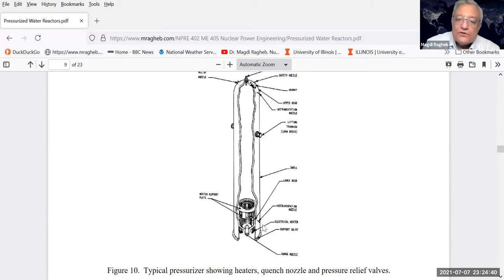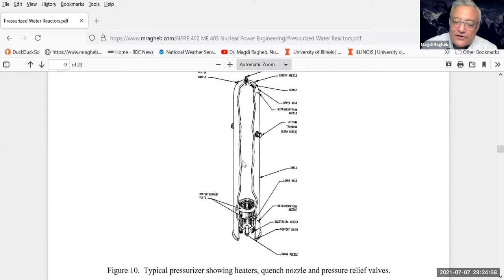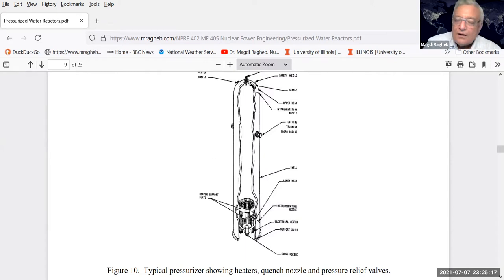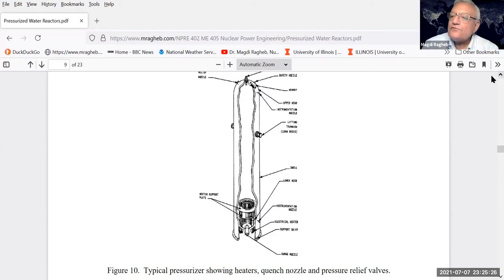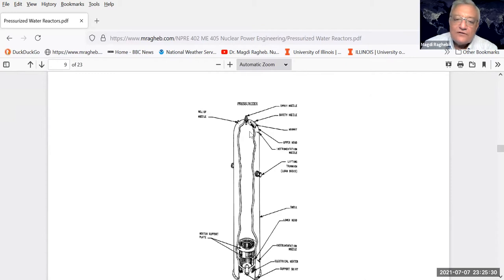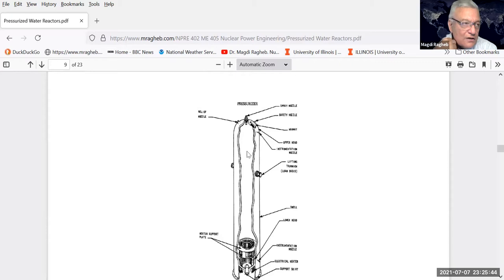We come to the pressurizer. How do you pressurize the system? We use electrical heaters - the operator pushes a button, circulates current in electrical heaters covered with water. The heaters heat the water, generating steam that fills up the top of the pressurizer. As pressure increases as a bubble on top of the water connected to the piping, the pressure spreads through the whole piping system. You decrease pressure using a spray nozzle on top of the pressurizer to condense steam and reduce pressure.